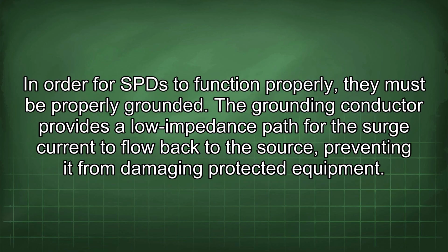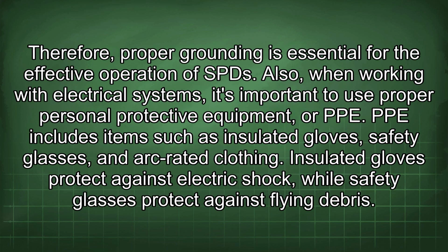In order for SPDs to function properly, they must be properly grounded. The grounding conductor provides a low impedance path for the surge current to flow back to the source, preventing it from damaging protected equipment. Therefore, proper grounding is essential for the effective operation of SPDs.